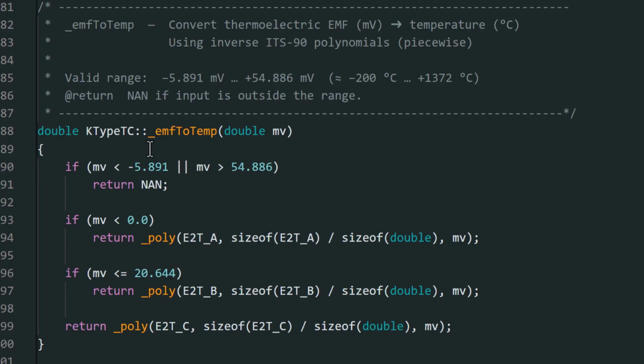Then here is our function for doing voltage to temperature, which we use to get our thermocouple value. First we check the range. If it's below 0, we use the array for negative. If it's below a certain voltage value, we use another one. Let me back up a second - this doesn't have to do with negative or positive temperature, it has to do with where the voltage falls in, giving you different polynomial values. That's why we have this A, B, and C array. Based on where our voltage measurement falls, we apply the different array of constants to the polynomial. How do I know these voltage values? They're in the data I got from the NIST website.